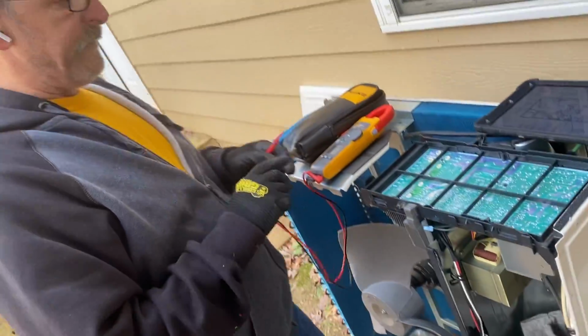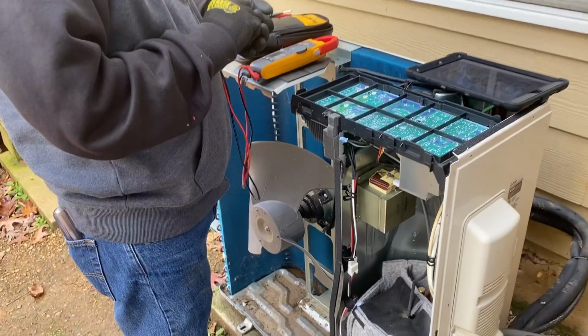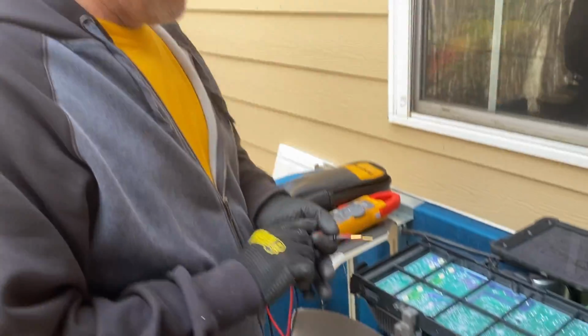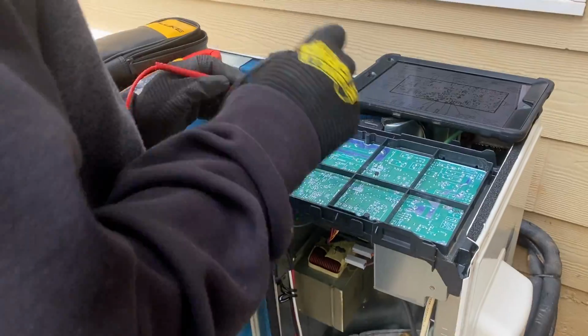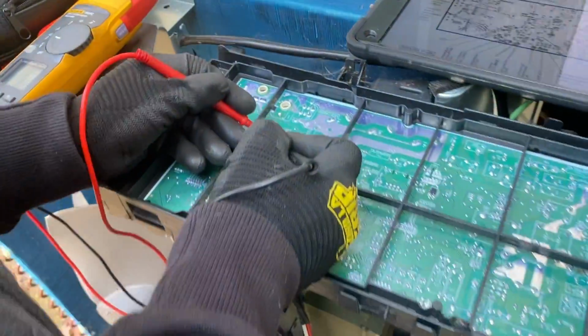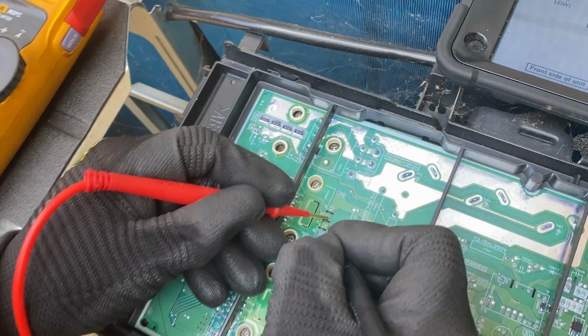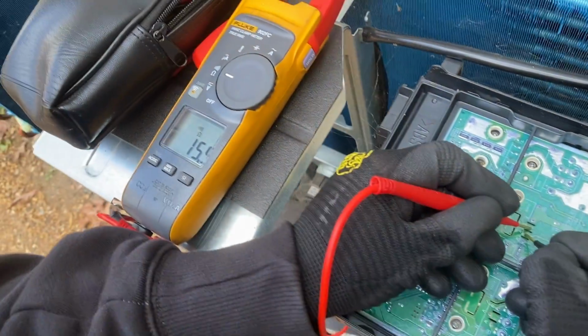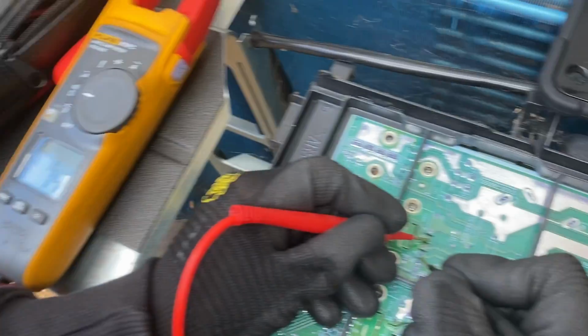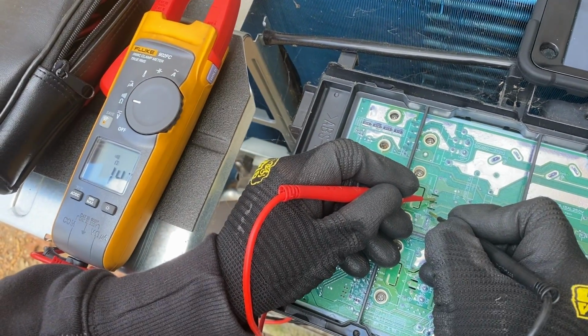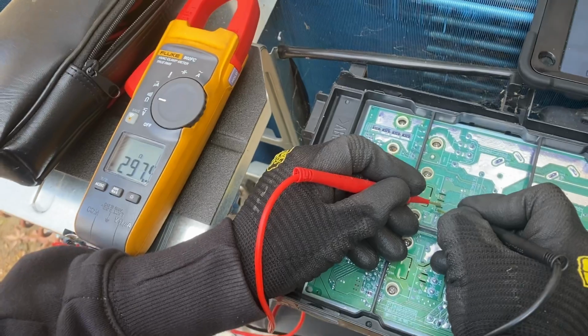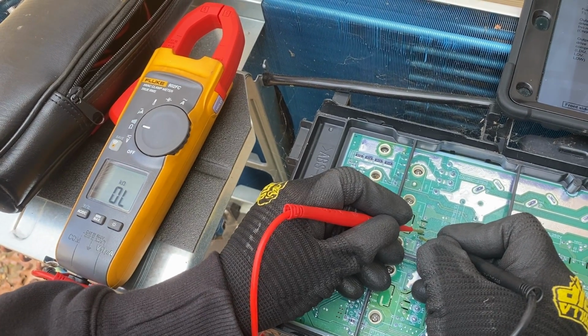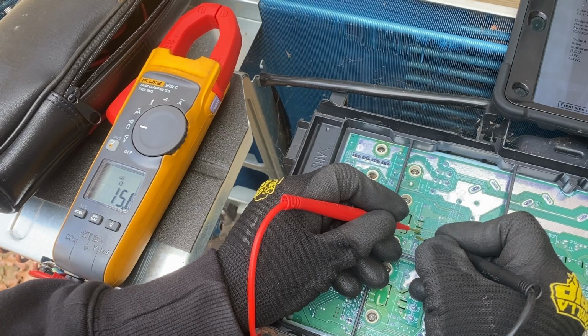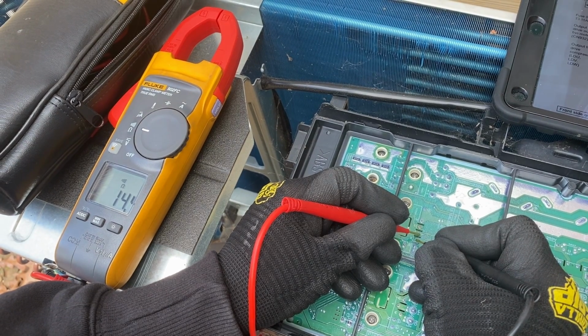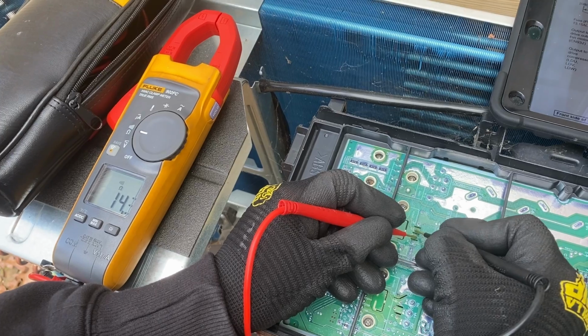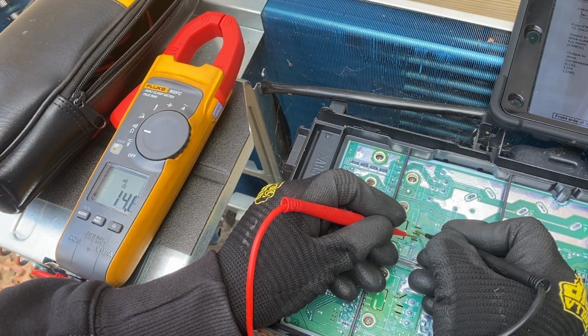If you want to test your fan on this particular one, the fan is a 3-phase motor. And then we just go from the same deal right there, U to V. We got 15 ohms. Got 14.3. And then 14.4, 14.2.